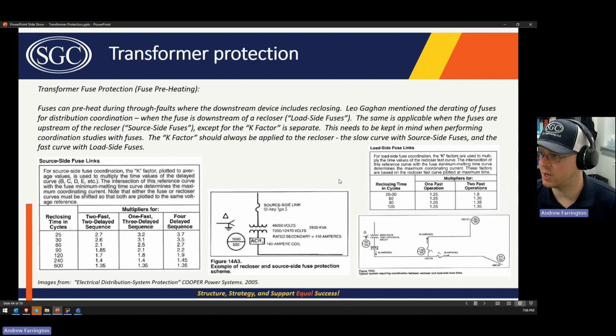This is related to the K factors. So these K factors are applied for load side fuse links. So this is where you have a transformer with a recloser on the low side feeding distribution customers, and there are different fused laterals that feed customers, right?